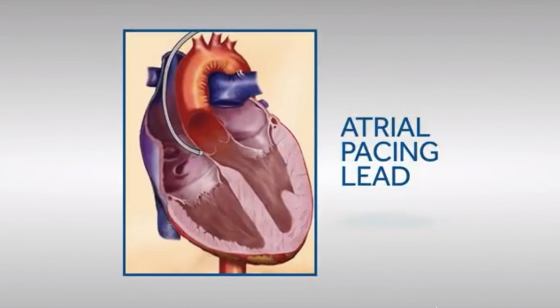The same process can be completed for an atrial sensing threshold, assuming that the pacing lead or wire is in the atrium. How to check the stimulation threshold? Sensing threshold is the minimum atrial or ventricular intracardiac signal amplitude required to inhibit or trigger a demand pacemaker, expressed in millivolts.